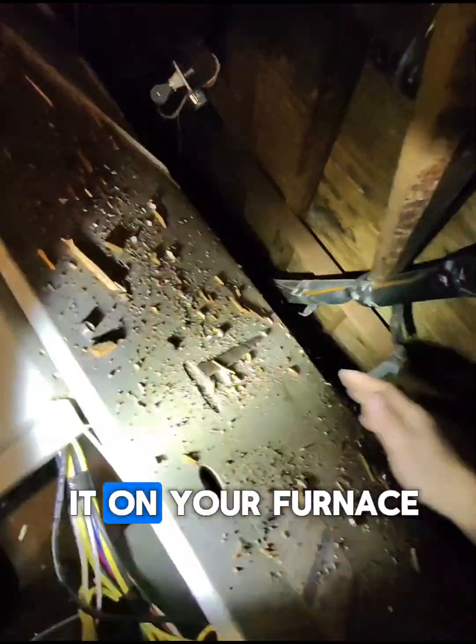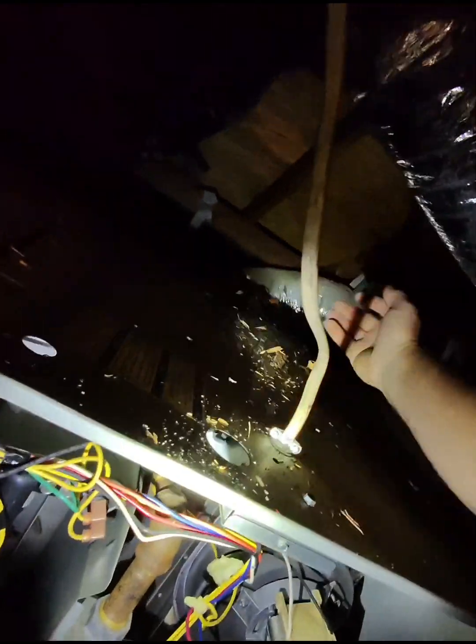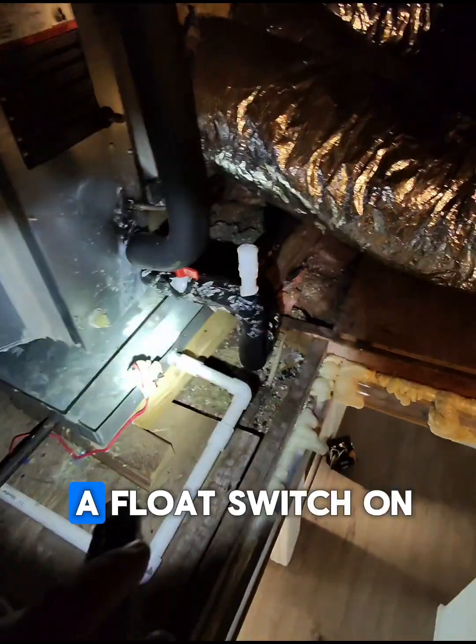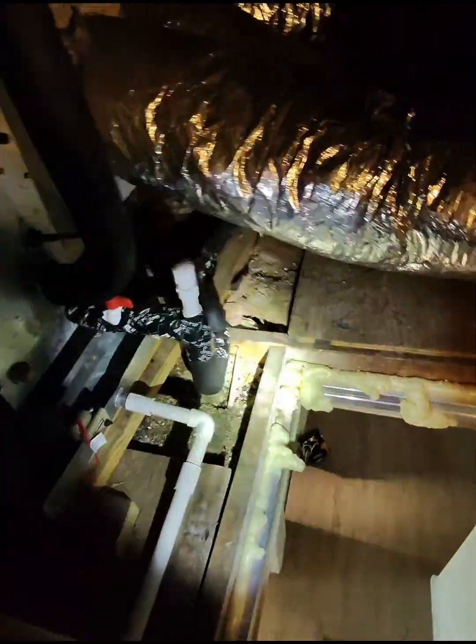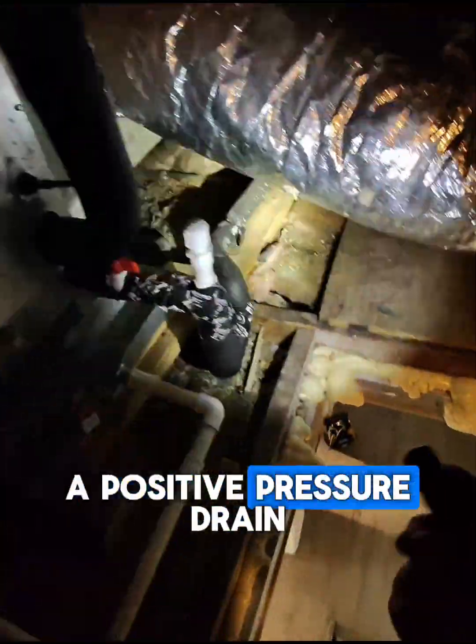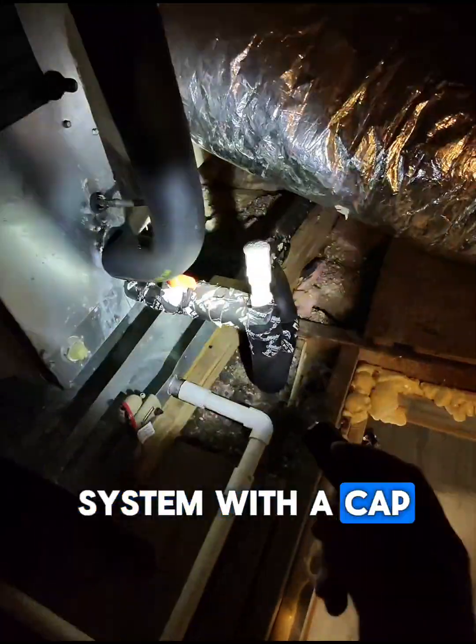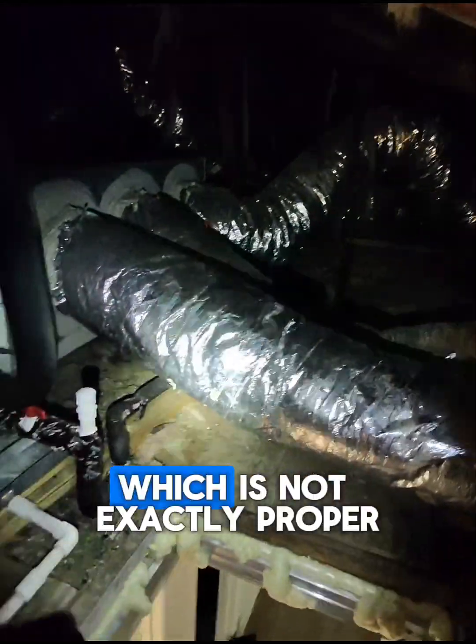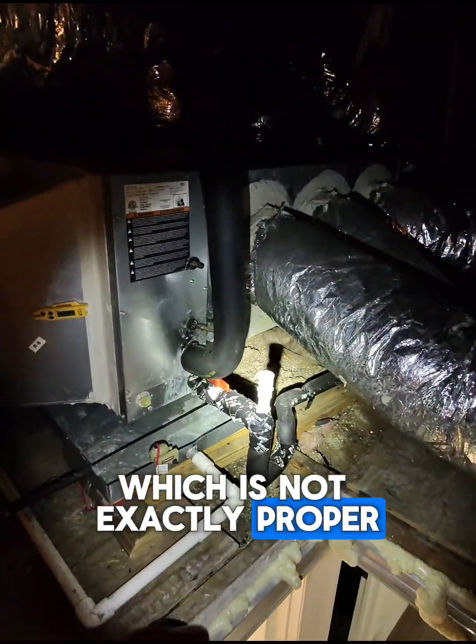You definitely don't want it on your furnace, because it does get a little warm. I'm not saying anything would happen, but an ounce of prevention, right? Gas line, got no sediment trap. You got a float switch on your overflow. P-trap, this is a positive pressure drain, and they've got a P-trap on this system with a cap before the P-trap, which is not exactly proper.